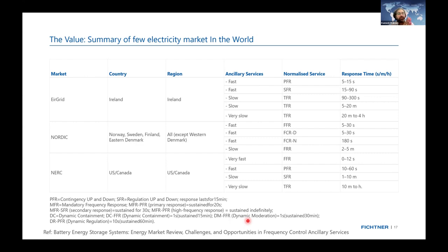These are the typical ones, and for regulation we have up to 1 hour. Why I'm emphasizing the time is that not only the control, your system also needs to respond. So here two things come into the picture. As a researcher, you can work on the controller to be as fast as possible. On active power, you need to size your system to accommodate this. Sizing is a huge challenge, because unless we know the load profile, we cannot size. If I am going to participate in frequency response or any ancillary services, I also need to size by considering the losses plus my response. I don't know how far my system may be required.